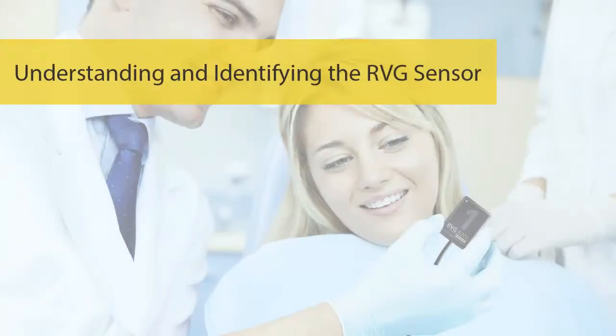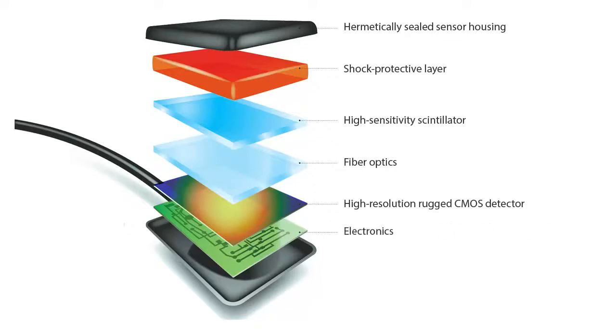Understanding and Identifying the RVG Sensors. RVG Sensors are built with durability and image quality in mind. The hermetically sealed sensor housing makes the sensor completely waterproof, allowing for more versatile disinfection methods. The shock protective layer helps prevent damage from bites and drops. The combination of high-sensitivity scintillator, fiber optic plate, and high-resolution CMOS provides the well-known RVG image quality and resolution.